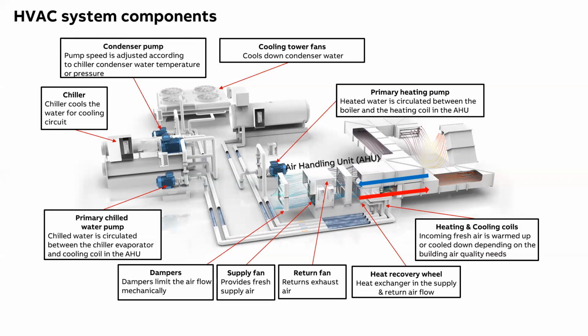So in other industries, torque control, speed control, and process automation are critical, which is the reason why a VFD is required. However, in the HVAC industry, energy efficiency is the primary reason why we go ahead with a VFD. Right from our chillers, it could be screw or centrifugal chillers, to our pumping systems, AHU, supply fan, return fan, HRW, cooling towers, in all these places a VFD can be used, and it gives a drastic reduction in the energy consumed. Now we'll see how it does that.